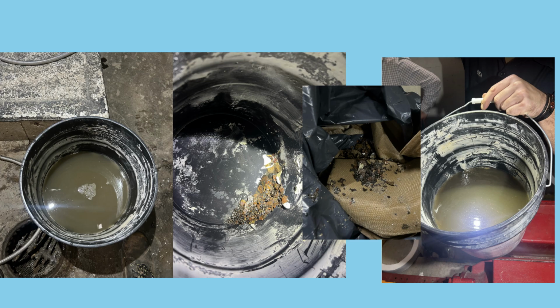Rust particles, scale, and sludge settle on the inner walls of the brazed plate or shell-and-tube heat exchanger. This creates an insulating layer between the refrigerant and the water. The refrigerant can't reject heat efficiently. Discharge, condensing temperature rises rapidly. The debris, like what's seen in the images, clogs Y strainers, isolation valves, or even microchannels inside the condenser plates. This reduces flow and increases differential pressure across the heat exchanger. The refrigerant pressure climbs even faster due to poor heat transfer.